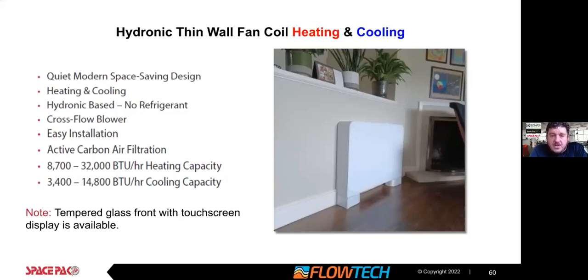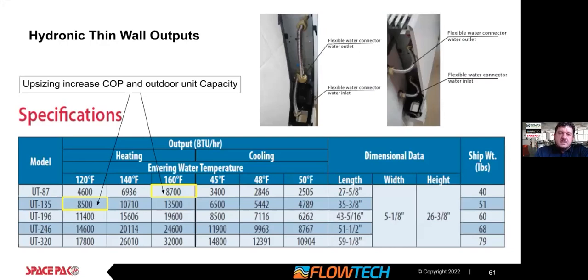Fairly simple to install, great retrofit solution. In our area, we're seeing these installed where you're not doing full cooling of the whole house, but certain times of the year, it's nice to have some cooling for the master bedroom, so it doesn't have to be a whole house cooling system. It can just be in some areas. Very important here too. And similar concept, you'll see the connections here on the left, 1-inch connections here on the left.